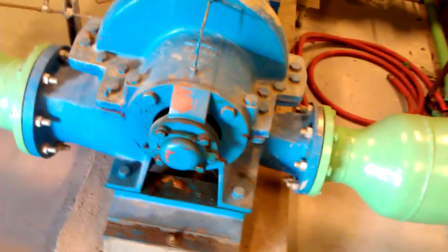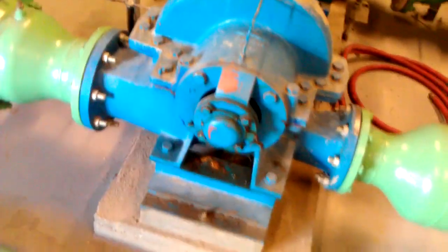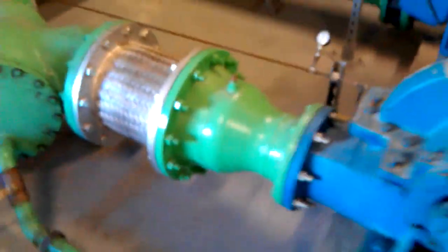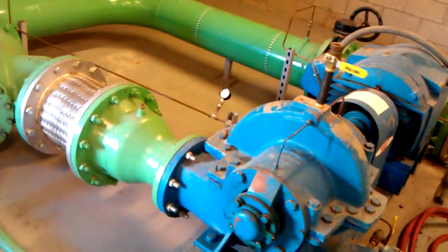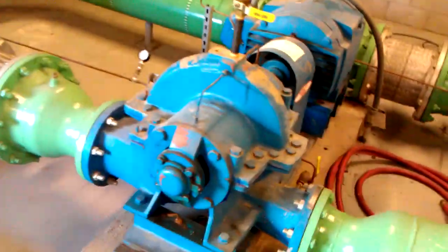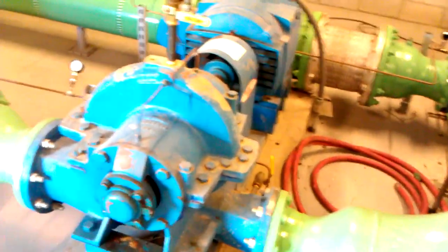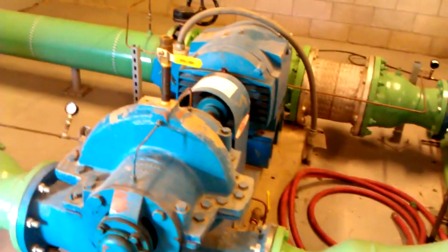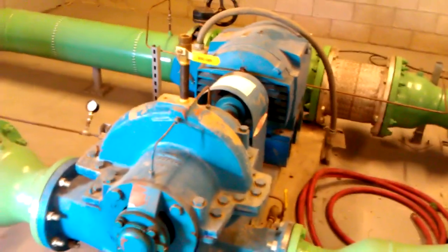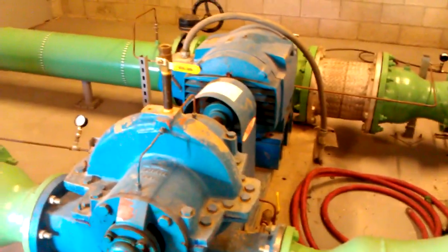This is pump number 2, which the EMS brings on with chiller number 2, which is not needed or running, but the screen must be good in it because the pressure looks pretty good. And my flow looks pretty good. Flow looks great outside actually at the tower, so I should only have to clean the one screen and then I'll switch it back over to the other one. Chiller should be starting up any minute.